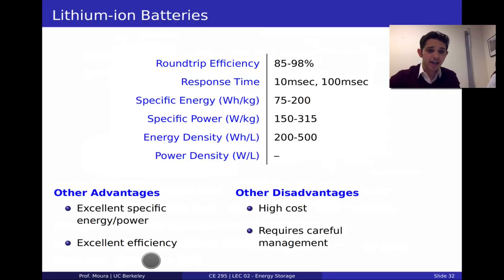Round-trip efficiency is higher for lithium-ion batteries, can be up to 98%. Response time is very, very fast, faster than lead acid, a tad slower than, say, electrochemical capacitor. So it's on the order of milliseconds. The reason that it's very interesting these days is because it can have excellent specific power and energy. So that's really why it's becoming more and more interesting. It also has relatively high round-trip efficiency.